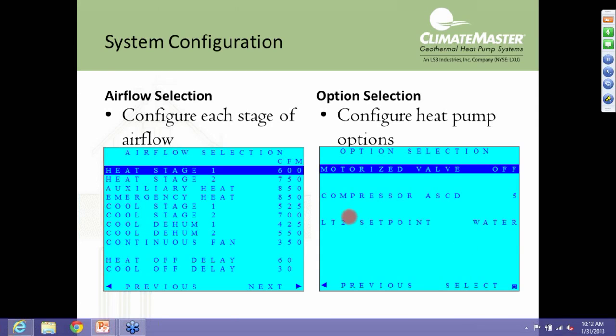The next item you see here is the LT2 set point. And again, this will not show up under any current product. The only time you can make a change to the LT2 set point will be in the future on a water-to-water product when we put the DXM2 communicating controls in our TMWs. Again, because you cannot freeze protect the air. This is our freeze protection for our air coil. You cannot freeze protect the air. So there is only that one set point, and the LT2 will trip out at 30 degrees on that refrigerant line.